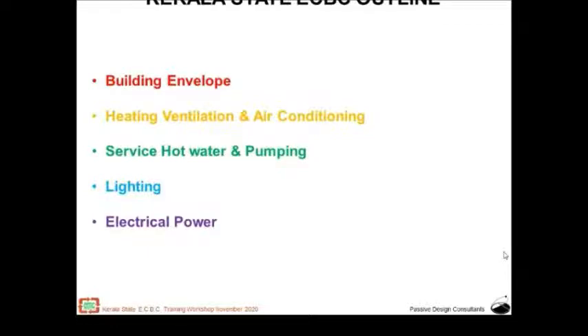These components, because they have to deal with the outdoor environment, should be designed for a state like Kerala. They should be designed such that we do not allow the heat from outside to come in, especially if the building is air conditioned. At the same time, we want ventilation to be available. So how should the envelope be designed? We also want daylight to come in from outside to inside, but we do not want the solar heat to come inside the building, to optimize our air conditioning loads. So the requirements related to the walls, roof, windows, the kind of glass we choose, the air tightness membranes or air tightness that we design for the building, and the doors and windows have to meet the requirements of the building envelope section of Kerala State ECBC.